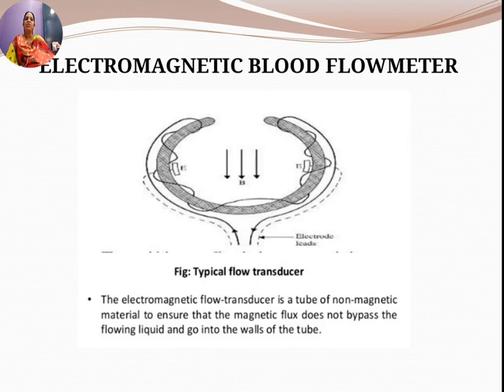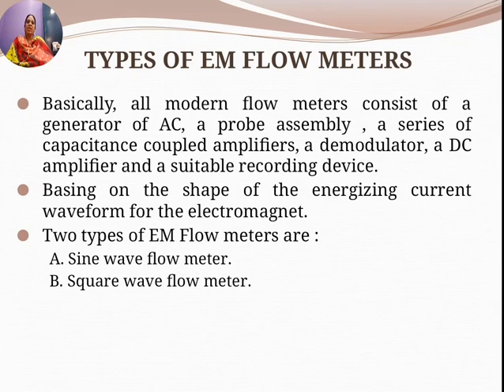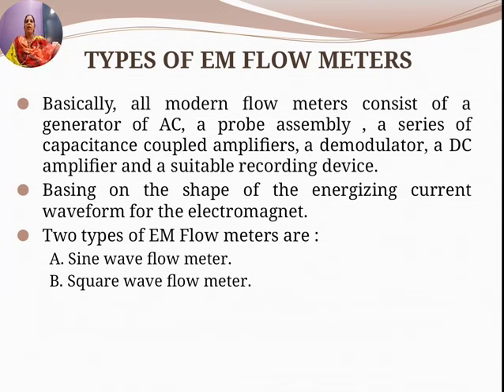The electromagnetic flow transducer uses a tube of non-magnetic material to ensure that magnetic flux does not bypass the flowing liquid and go into the walls of the tube. All modern flow meters consist of a generator of AC, a probe assembly, a series of capacitor-coupled amplifiers, a demodulator, a DC amplifier, and a suitable recording device.